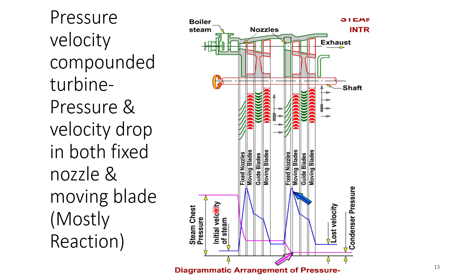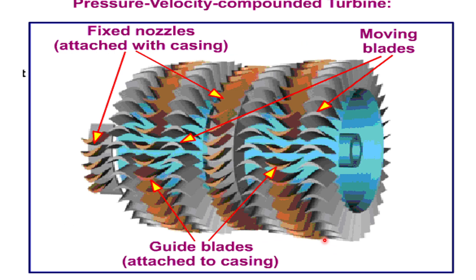Almost all stages of the turbine except the first are pressure-velocity compounded. As steam passes through each nozzle, pressure drops and velocity increases. In the moving blade and fixed blade, velocity drops and pressure changes accordingly. The practical turbine uses pressure-and-velocity compounding where there is a series of nozzles and moving blades alternating: nozzle, moving blade, nozzle, moving blade — repeated stage after stage.